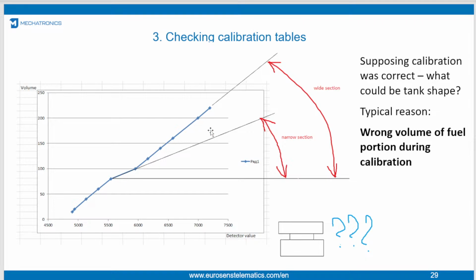Remember that every bend of the calibration plot is a dramatic change of the tank shape. For example, a plot like this one. The slope of this line, tank calibration, in fact means tank width. And we can see that the lower part of the tank and the higher part of the tank have much bigger width than the medium part of the tank. So if this calibration is correct, our tank shape is something like that, seen from the left side or front. It's very strange, and most likely it's an error.